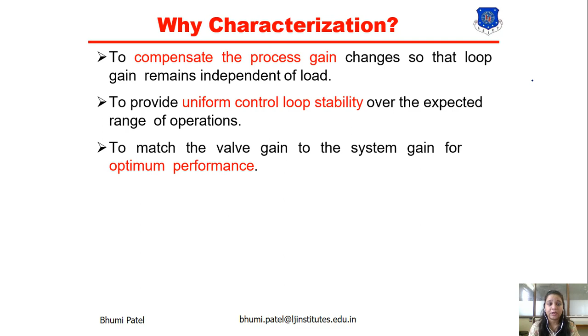Next one is to match the valve gain to the system gain for optimum performance. Using the control valve, we also require optimal performance of the system. So we can match the valve gain to the system gain using the characterization. Now how can we characterize the control valve? The first is the trim shaping. Now what is the trim shaping?